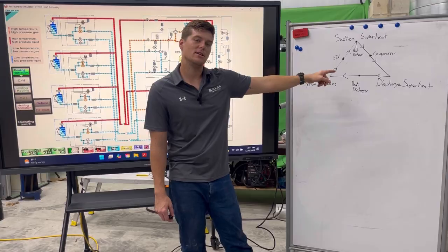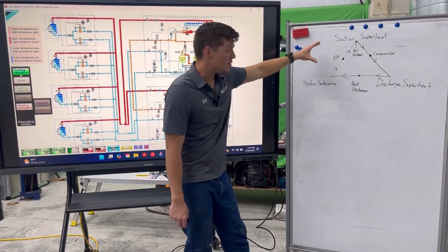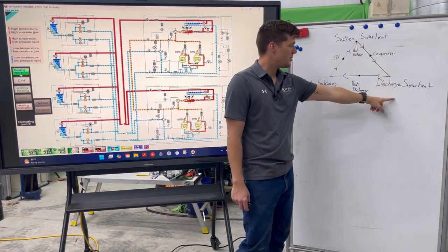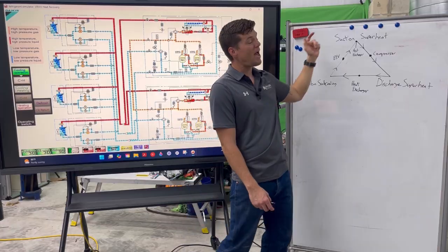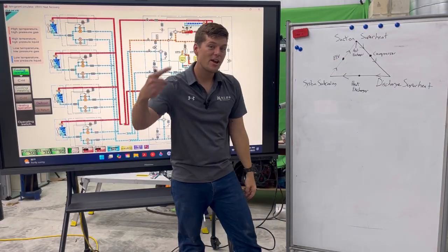This is how they are connected. Know it, live it, breathe it. Suction superheat to discharge superheat to system subcooling to back to suction superheat. It's this never-ending repetitive cycle.